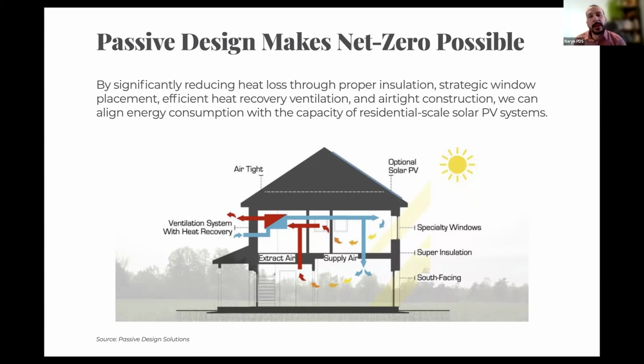It's interesting because an HRV is a code minimum requirement in Canada, so every home built has one, but we work with clients in the US too, and many states don't have minimum code requirements for an HRV. So when you look at the upgrade cost to Passive House, if the code minimum is further behind, it becomes more onerous to reach the same energy standard. For folks looking at code minimum and saying they don't need an HRV, extra insulation, or triple pane windows, the leap to that level of energy performance is actually bigger than when starting with more rigorous codes.